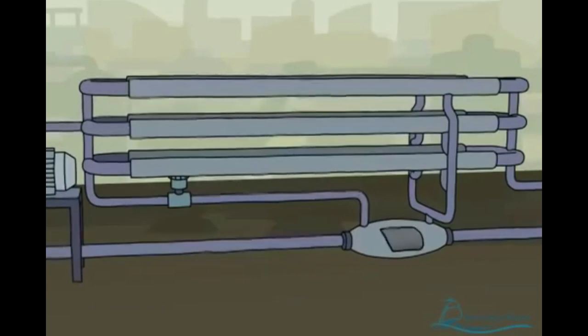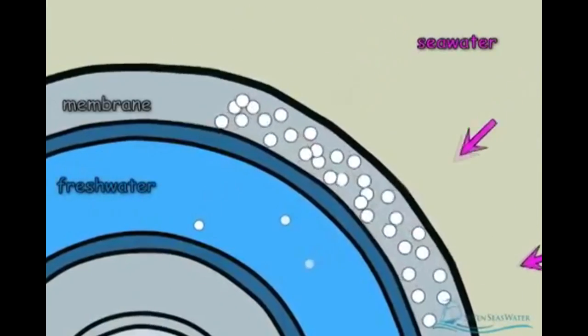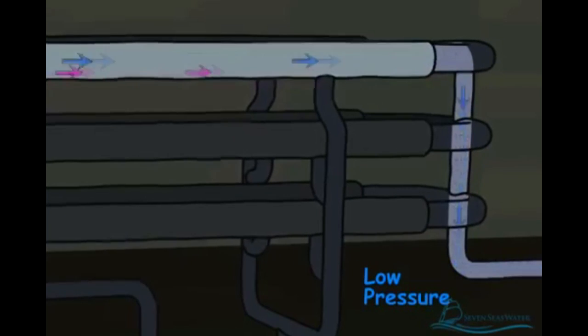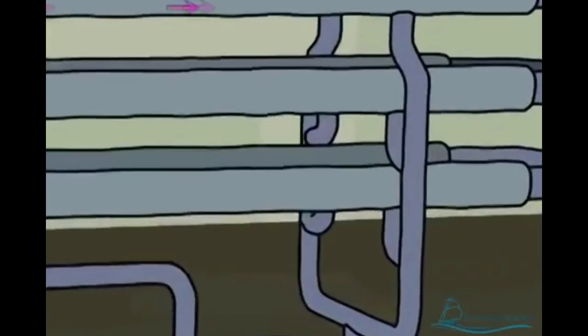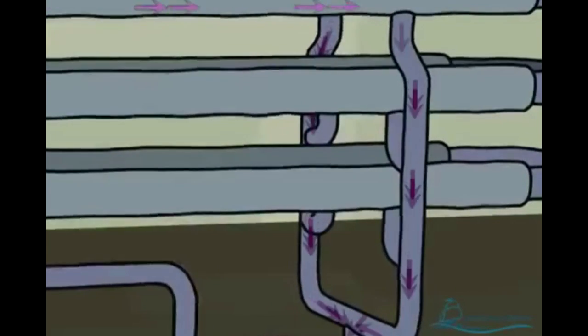As the pressurized seawater enters the pressure vessel and flows across the membrane surface, the water molecules are forced into and through the membrane envelopes, leaving the salt molecules behind. The desalted water passes through the membrane and emerges at low pressure, where it is collected in a tube and directed to one end of the pressure vessel. The concentrated salt stream that is rejected from flowing through the membrane continues to pass across the membrane surface, where it is collected separately.